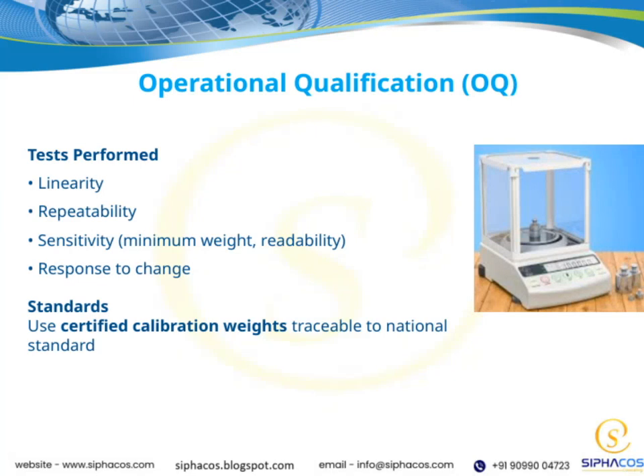Now, let's take a closer look at operational qualification, or OQ, and the tests involved in this phase. First up is linearity. This test ensures that our equipment provides accurate measurements across the entire range we plan to use it. It's crucial because we want to be confident that the instrument's responses are proportional to the actual weights or signals. Next, we have repeatability. This means checking that the device gives consistent results when we perform the same measurement multiple times under the same conditions. Consistency here is key to reliable operation.